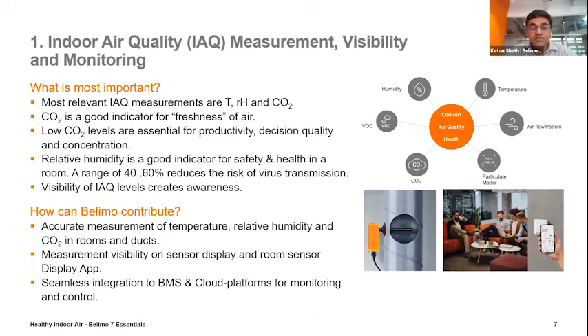When we talk about IAQ, the first primary 3 parameters which come to our mind are temperature, RH and CO2. VOC is also playing an important role. But nowadays I have seen, after all this, that most premises are not putting in carpets. They are going with normal tiling, normal flooring, so that the VOC issue can be avoided. As Mr. Mittal mentioned, CO2 is one of the important aspects for the freshness of the air. The lower the CO2 level, the more the productivity and efficiency, because when the CO2 level increases, there is a lack of concentration, headache and other things, which has been seen in most cases. So a low CO2 level increases productivity.